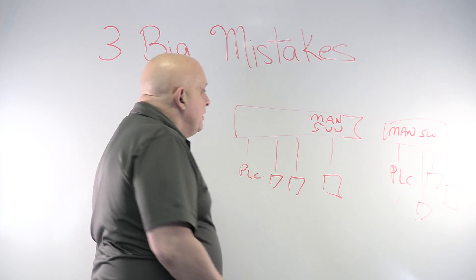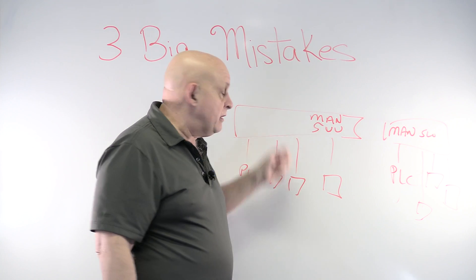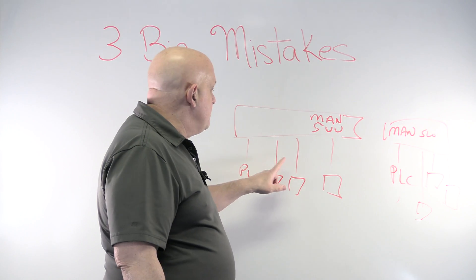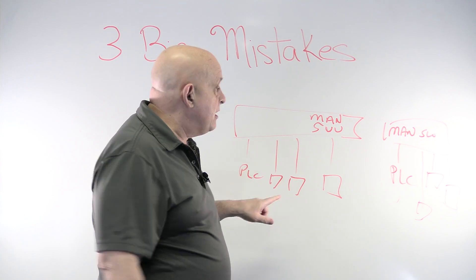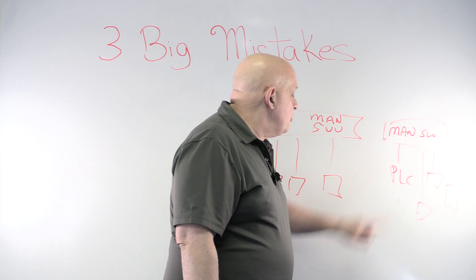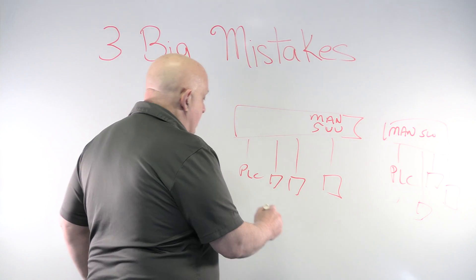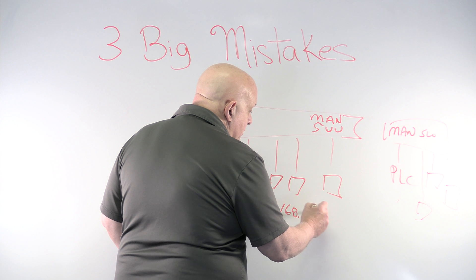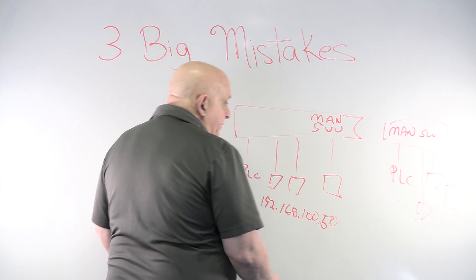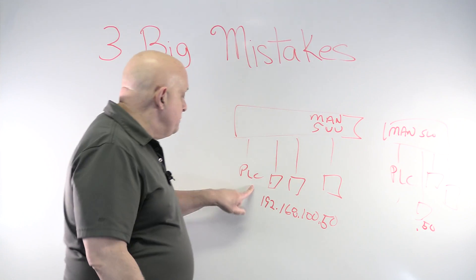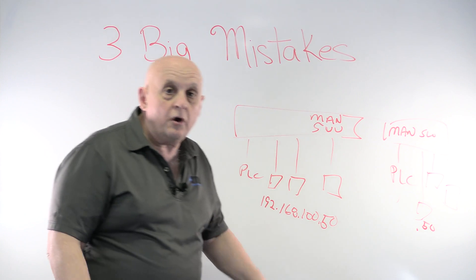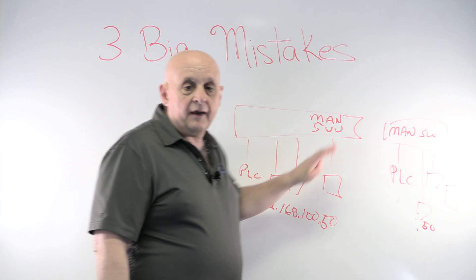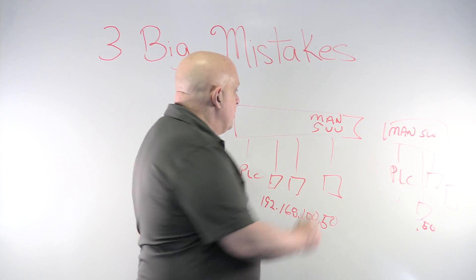This segmentation approach offers a number of advantages. Because you're using managed switches you can monitor each segment much better. You can also address devices identically across cells doing the same function — so if you find a bug in one PLC program you can just copy it to the other because everything is addressed the same. For example, if all your drives use private addresses like 192.168.100.50, a drive in the next cell is also .50, and you just copy the PLC program over. No re-addressing needed.